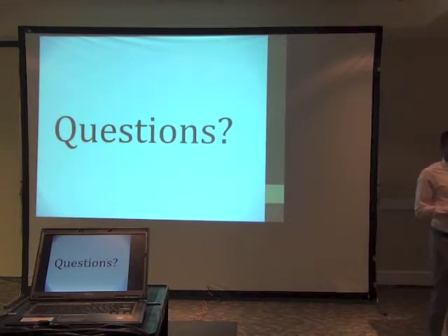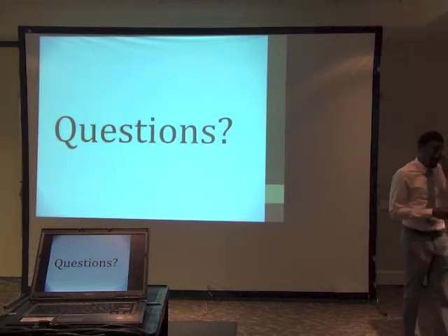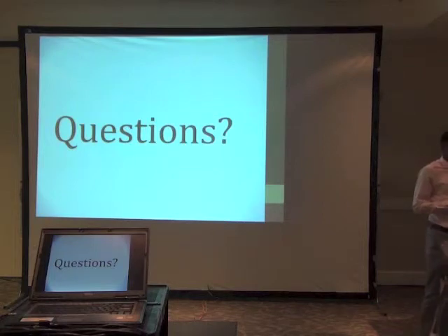Any more questions? Yeah, actually, I had a couple of different questions, whatever order you want to answer in. Do you have any past devices that use compression for X-rays or any other methodology that's been used in radiography for compression? Yes. Compression has been used in mammography for years, and there is some research involving compression of the abdomen using straps. This is the first device for the abdomen that uses 2 points.